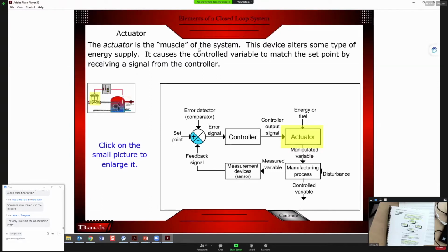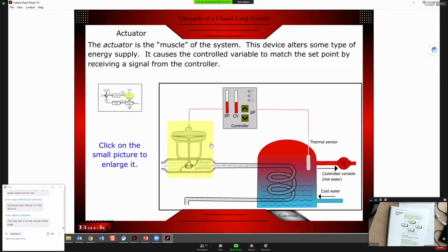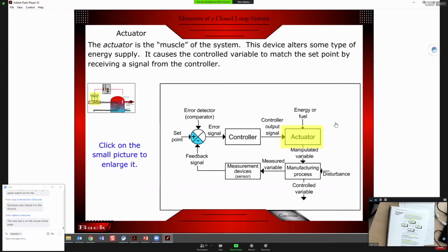The actuator, they usually call the muscle, and those are mostly valves, because we can open them and close them. In here, these are the valves to make changes to how much steam or heating flow we can send through the system. Other final control elements or actuators could be motors or other types of relays. Their purpose is to make the adjustment to the process.